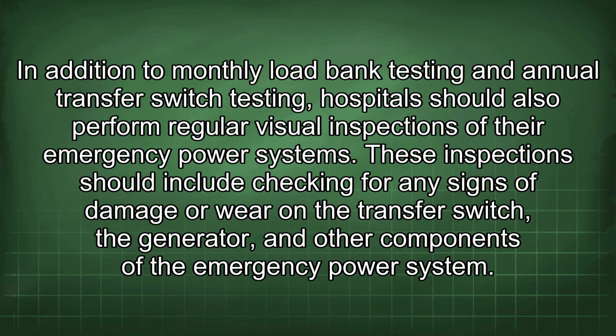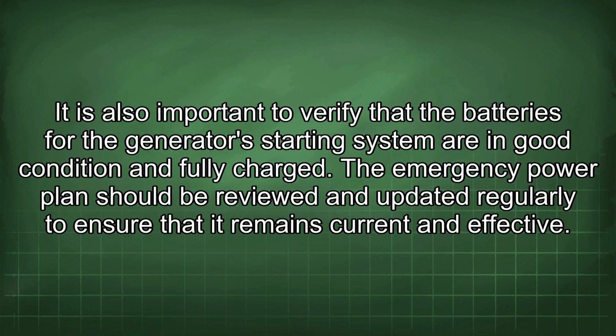These inspections should include checking for any signs of damage or wear on the transfer switch, the generator, and other components of the emergency power system. It is also important to verify that the batteries for the generator's starting system are in good condition and fully charged. The emergency power plan should be reviewed and updated regularly to ensure that it remains current and effective.